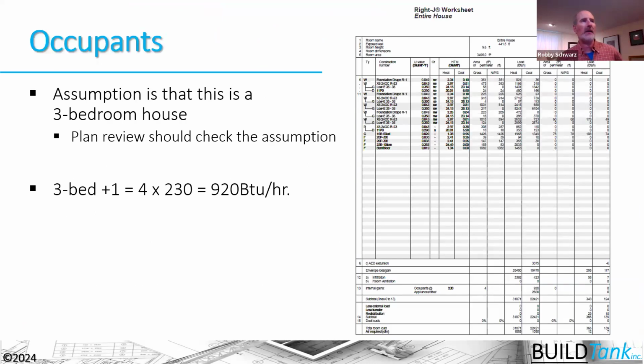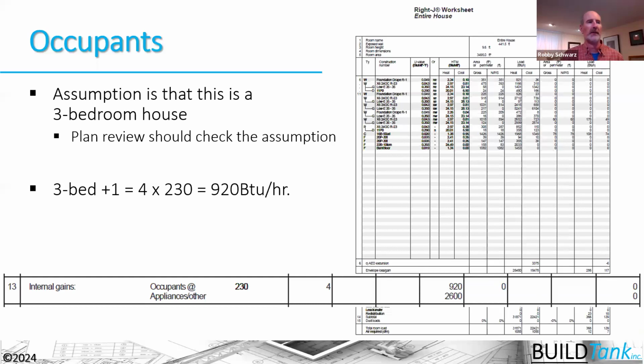So the assumption again in this case is that it's a 3-bedroom house, so it would be 920 BTUs. If we look at the worksheets for our Manual Js, we can see that the occupants in this were added. I blew it up here a little bit so it's easier to see. We've added 4 occupants at 230 BTU per hour per occupant, and you can see the 920 over there in the total.